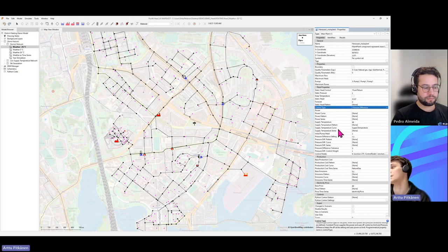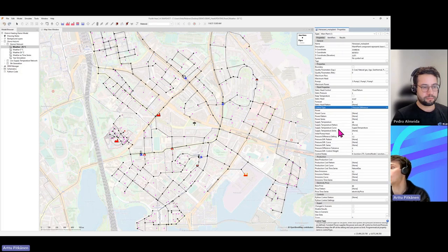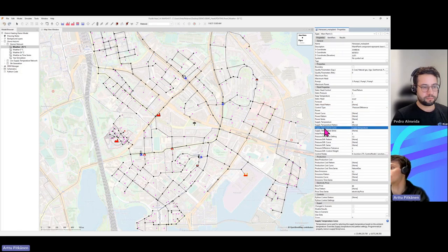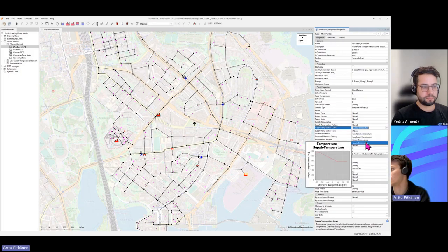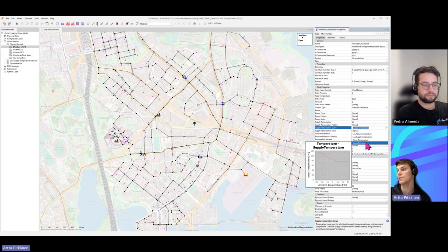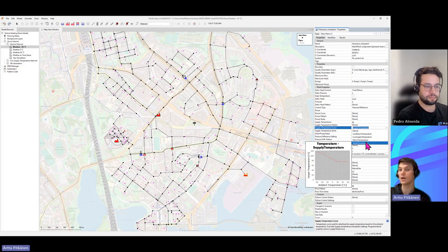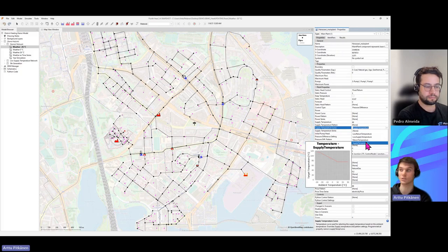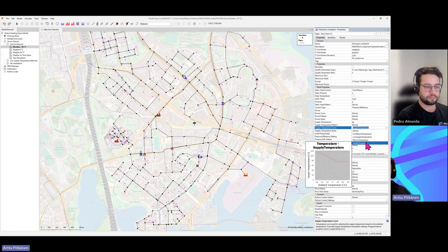You can also define the supply temperature using a time series, constant values, or heat curves as a function of ambient temperature. For example, here the x-axis shows air temperature from minus 30 to 30 degrees. In Finland during cold winters at minus 30 degrees, we push around 115-degree water into the system, while during hot summer days we use something like 75-degree water.